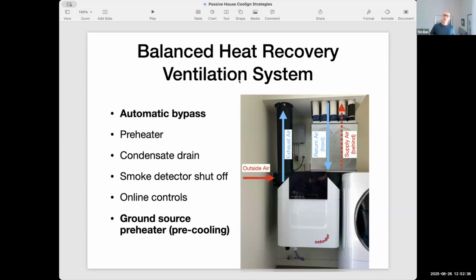The first thing for those of us in the passive house realm that we can activate is our balanced heat recovery ventilation system. Most of those systems have an automatic bypass, meaning when conditions allow for meaningful night cooling, it opens the hatch, forgoes the heat exchanger, and flushes the house with cool air. I can actually sense that in my own home sometimes, since the system goes into overdrive, actively trying to flush more cold air into the building. So the bypass feature, when you spec a ventilator, is a meaningful way to get more cooling into the building.